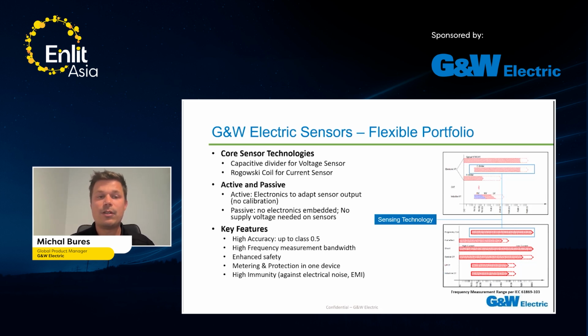So what are the key features? High accuracy up to class 0.5. With active sensors, we can achieve even better values, in fact lower values, so 0.2 and so on. There is a huge frequency measurement bandwidth, especially for the active sensors and capacitive ones. We will talk about it later. It's a safe solution, right? It's absolutely safe for maintenance and installation. You have metering and protection in one device, and it has high immunity against electronic noise and so on.